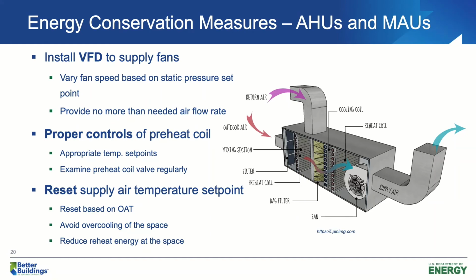Install VFDs on supply fans. If we have VFDs on our supply fans, we can modulate the fan speed and air flow rate to match the cooling load. We do not want to provide too much cool air to spaces because we might make the space temperature too low. This way, we might need to reheat the air temperature up. That means we are doing heating and cooling simultaneously. That is definitely some energy waste.